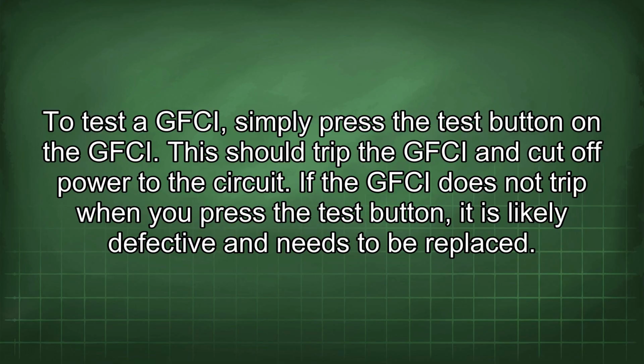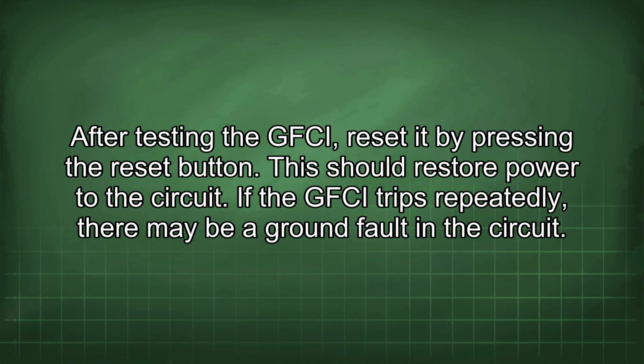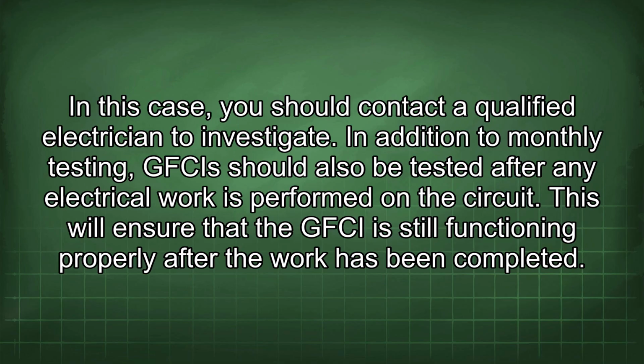If the GFCI does not trip when you press the test button, it is likely defective and needs to be replaced. After testing the GFCI, reset it by pressing the reset button. This should restore power to the circuit. If the GFCI trips repeatedly, there may be a ground fault in the circuit. In this case, you should contact a qualified electrician to investigate. In addition to monthly testing, GFCIs should also be tested after any electrical work is performed in the circuit. This will ensure that the GFCI is still functioning properly after the work has been completed.